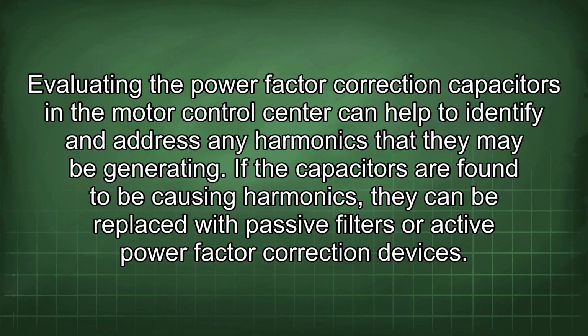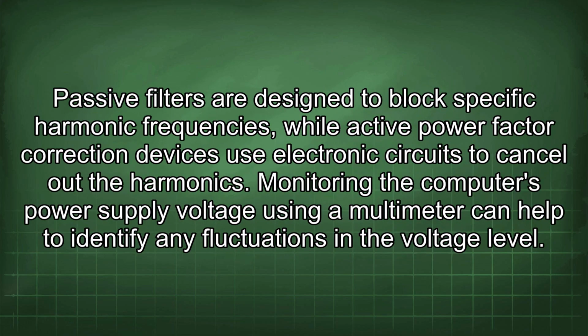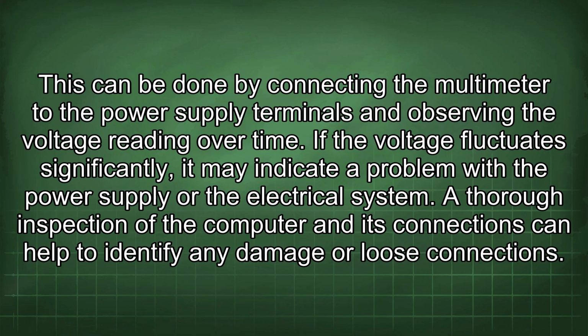Evaluating the power factor correction capacitors in the motor control center can help to identify and address any harmonics that they may be generating. If the capacitors are found to be causing harmonics, they can be replaced with passive filters or active power factor correction devices. Passive filters are designed to block specific harmonic frequencies, while active power factor correction devices use electronic circuits to cancel out the harmonics. Monitoring the computer's power supply voltage using a multimeter can help to identify any fluctuations in the voltage level. This can be done by connecting the multimeter to the power supply terminals and observing the voltage reading over time. If the voltage fluctuates significantly, it may indicate a problem with the power supply or the electrical system.